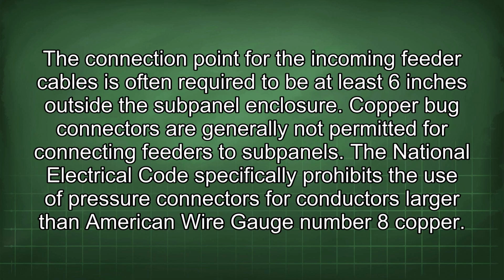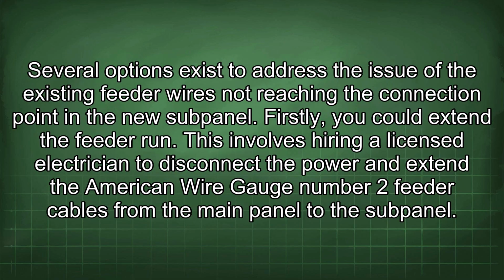The connection point for the incoming feeder cables is often required to be at least 6 inches outside the subpanel enclosure. Copper bug connectors are generally not permitted for connecting feeders to subpanels. The National Electrical Code specifically prohibits the use of pressure connectors for conductors larger than American wire gauge number 8 copper.